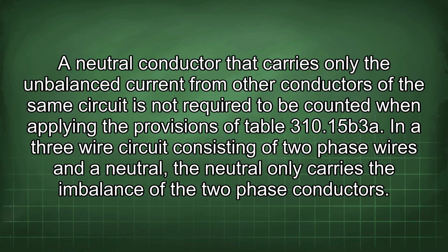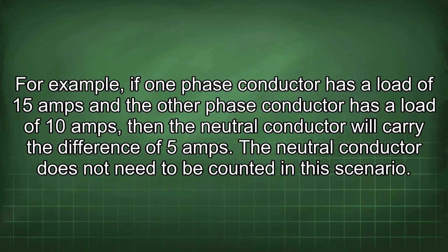310.15(B)(3)(a). In a 3-wire circuit consisting of 2 phase wires and a neutral, the neutral only carries the imbalance of the 2-phase conductors. For example, if one phase conductor has a load of 15 amps and the other phase conductor has a load of 10 amps, then the neutral conductor will carry the difference of 5 amps. The neutral conductor does not need to be counted in this scenario.